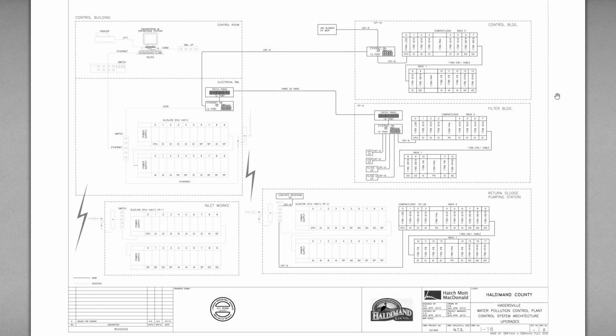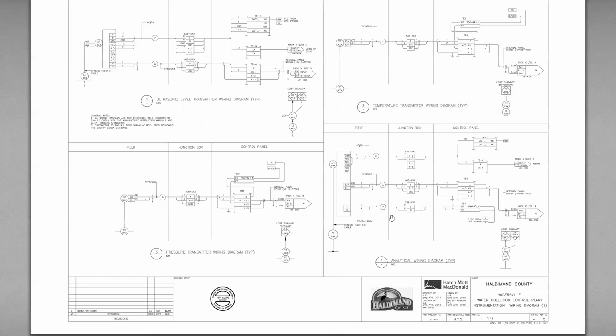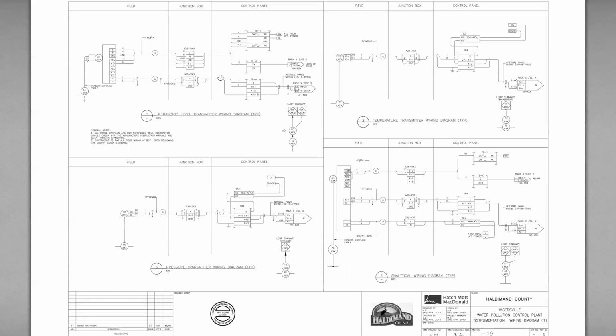Here's a layout drawing for the network. Pretty high level stuff. We've got PLCs in different sections of the plant. Some of them are SLC 505s, the other ones are CompactLogix. This is breaking down. I'm going to show you better examples of these, but when I was talking about loop drawings, so when you move from an electrical drawing that says, hey, you need to run power to this device and pull a 4 to 20 signal out of this device, this type of loop drawing would specify how you're supposed to do that wiring.